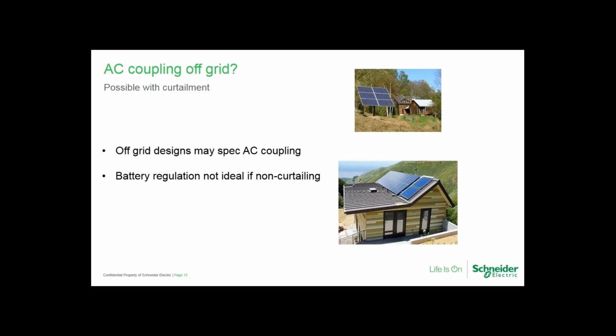Why not just DC couple? If you're specifying an off-grid AC coupled system, make sure the grid-tied inverter has curtailment capability, or make sure the battery type that you select is partial state of charge tolerant. Some manufacturers of lead acid chemistries, as we mentioned, require a full charge to maintain their warranty status. So be sure that the battery life will not be adversely affected by repeated bulk charge cycles.